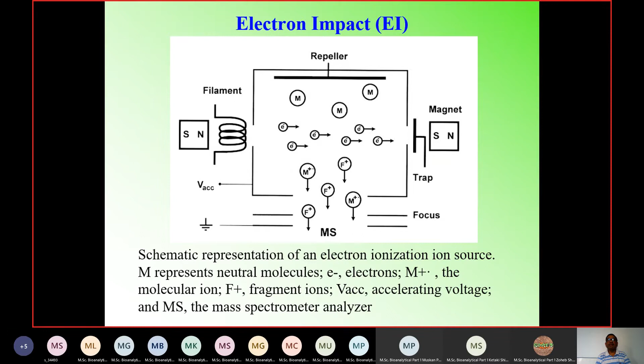There are voltages which will be applied. There is an accelerating voltage, VAC, here. Because of the accelerating voltage, all the ions will be accelerated from here to here, and in their path they will find M, and there is an interaction followed by fragmentation of the ions. So this is how the electron impact mode looks. It produces a highly stable and highly reproducible mass spectrum.